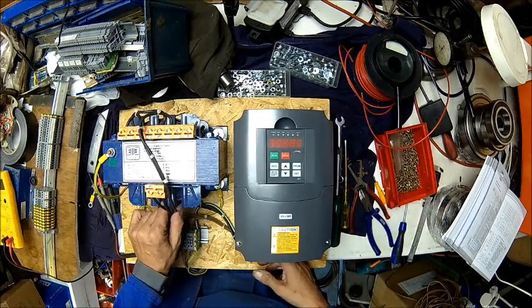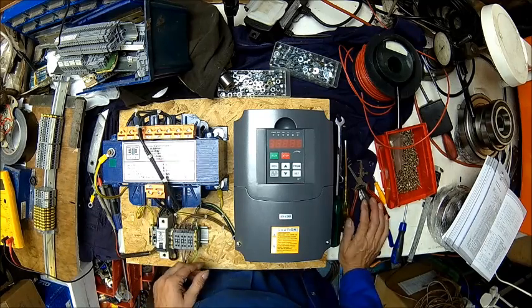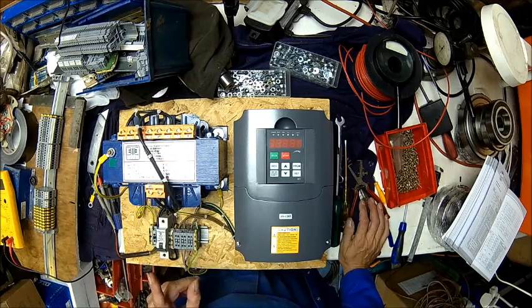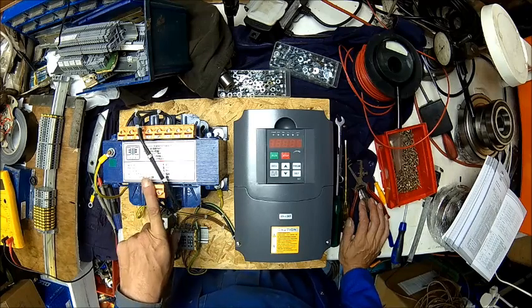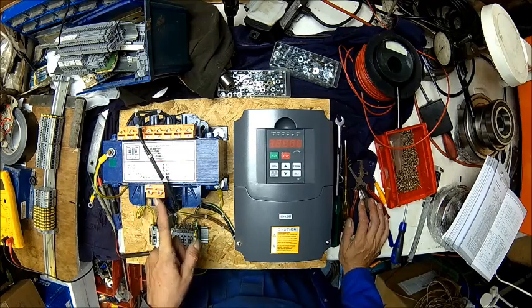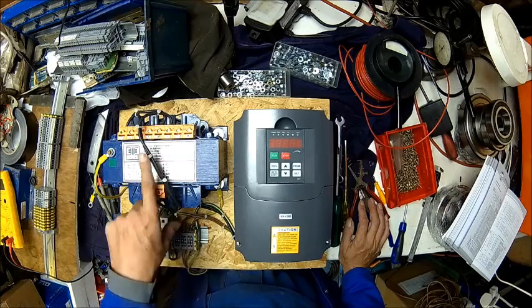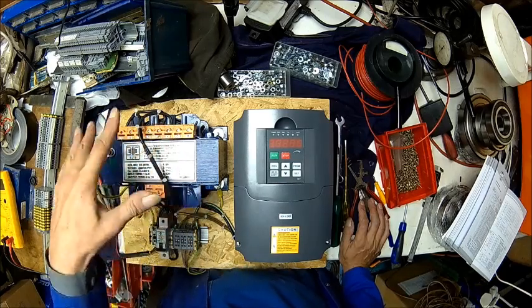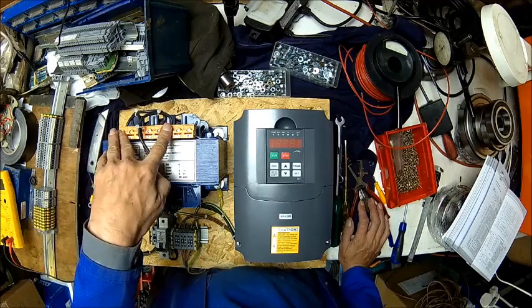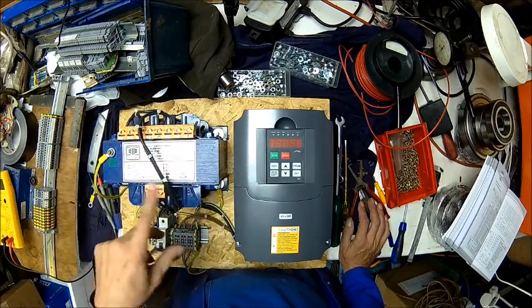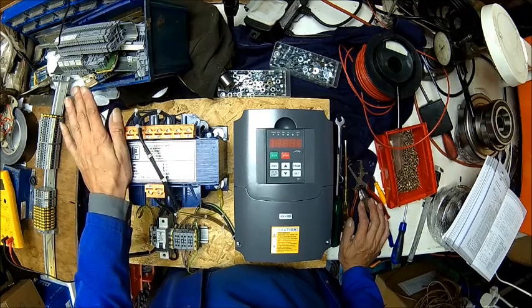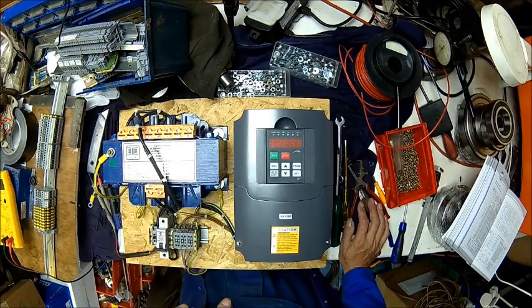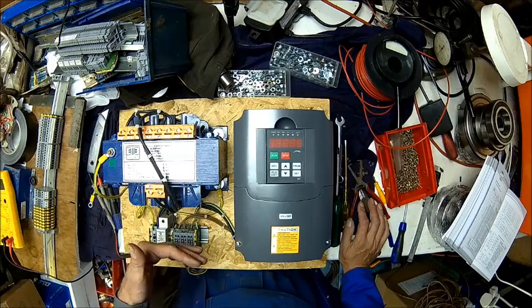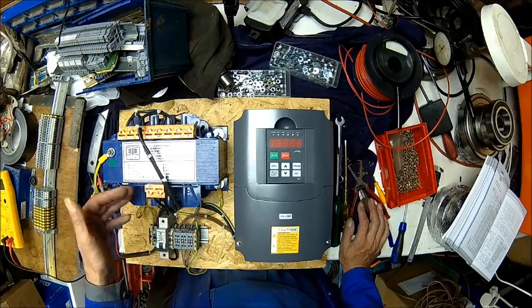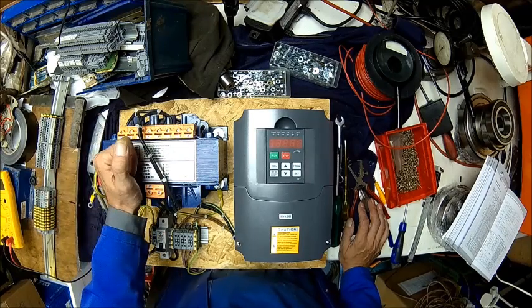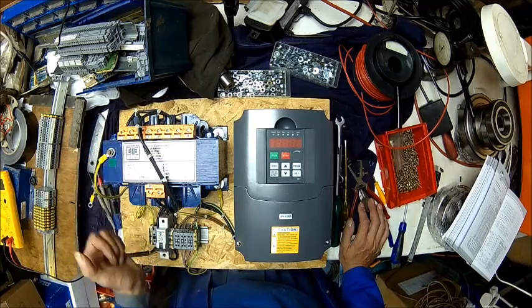So we tidied up the cable work a little bit. Probably one word, the transformer only needs about half the power, because we're feeding 230 volt into the transformer and getting 230 volt out or 220 volt out, and put that in series with the mains, so the transformer is only doing half the work for this particular setup here. You can do it with 2 transformers, or with a 400 volt or 230 400 volt transformer, but then you need a full rating on the transformer. Saves you a bit of money on the transformer.